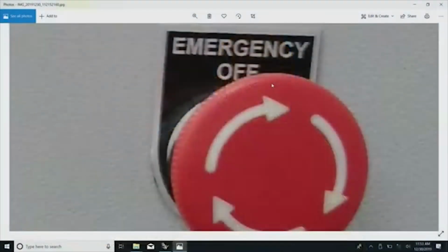But if you see here, intentionally, any of these emergency stop devices project out of the panel. You understand, we should never hide them behind a glass and write there saying break in case of emergency, break glass. It does not make a difference. It needs to be sticking out like this. The advantage of something sticking out is, in a real emergency somebody can just press it, and you see the large size also.